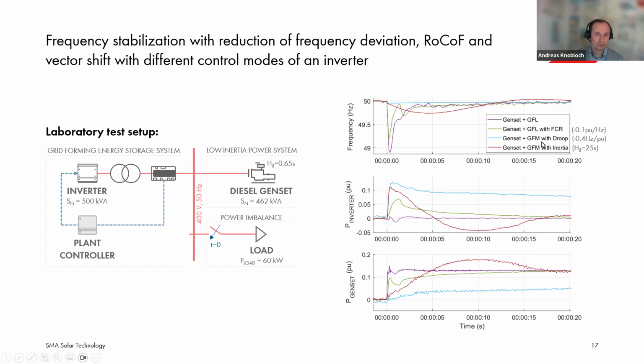If we now operate our system in grid forming mode with a droop control, we see the inverter responding and absorbing a huge amount of the power imbalance that happens in the grid, almost 13% as we see from the load. And this power that is absorbed by the inverter is not seen anymore by the diesel generator. Since the diesel generator does not see the power imbalance, its rate of change of frequency and change in its frequency is quite small. And this seems to be, in our laboratory test, the best result for frequency stabilization.